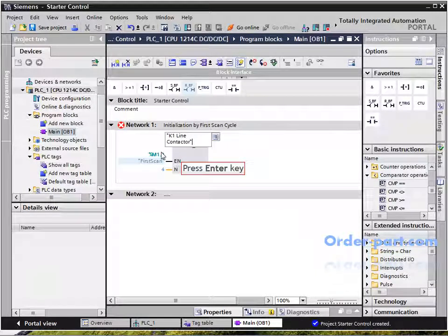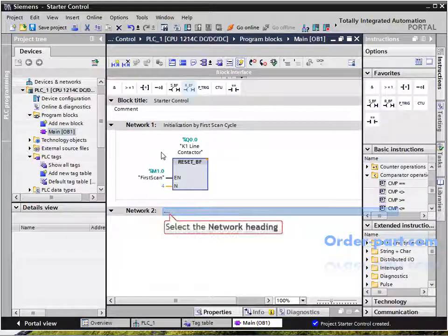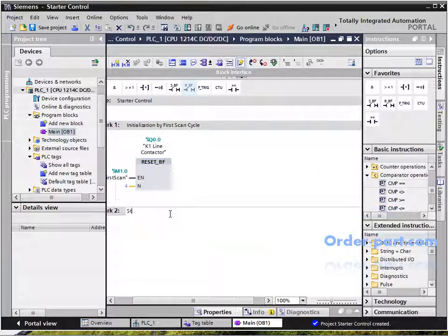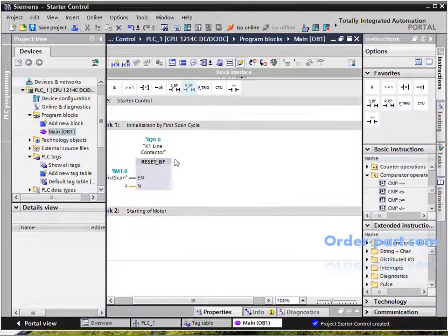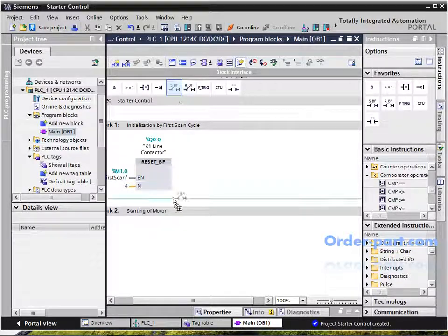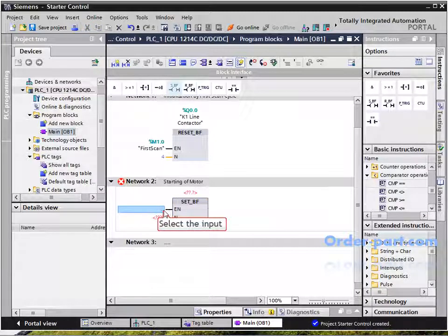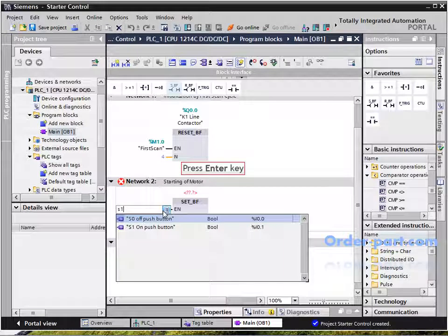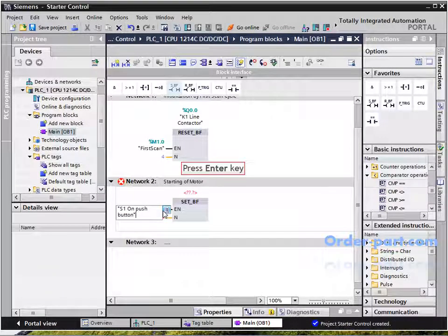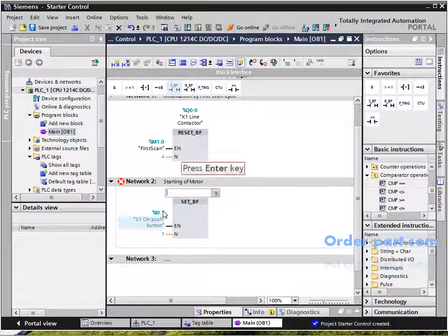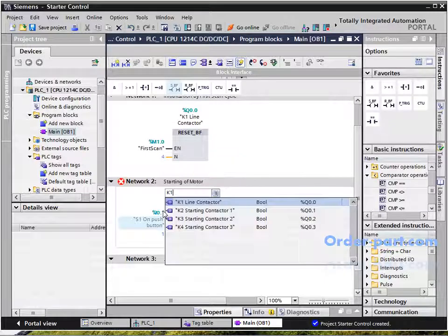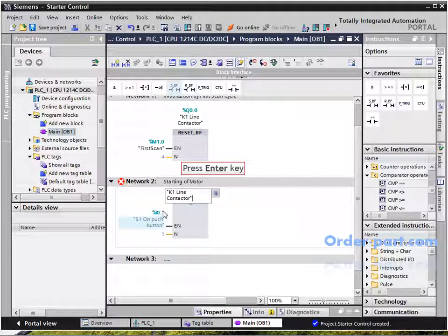Network 1 will initialize all contactors to the reset position at the start of the PLC using the first scan cycle. In Network 2, the process of starting the motor by pressing the ON button will close the contacts of the K1 contactor.